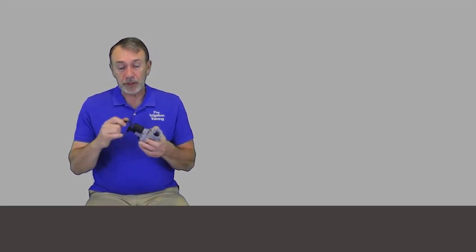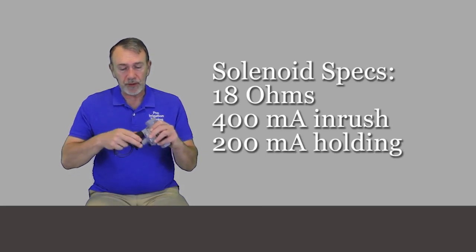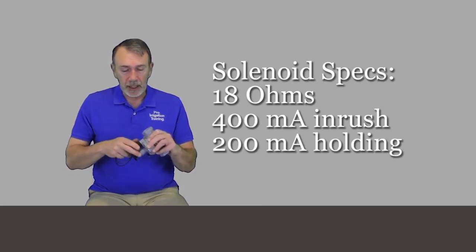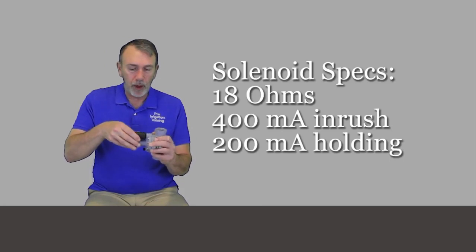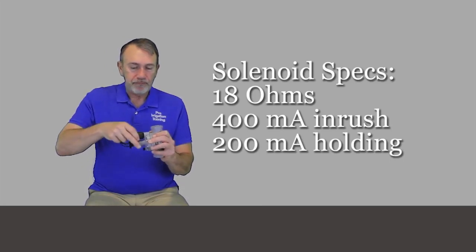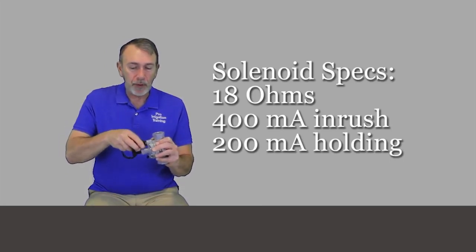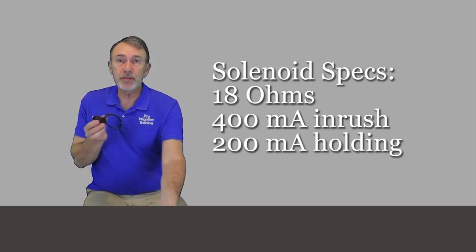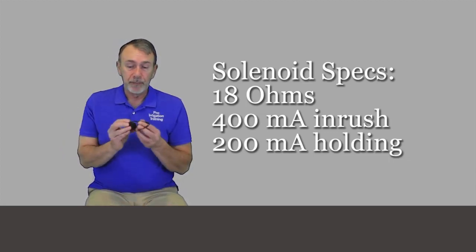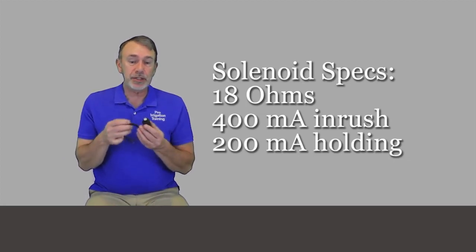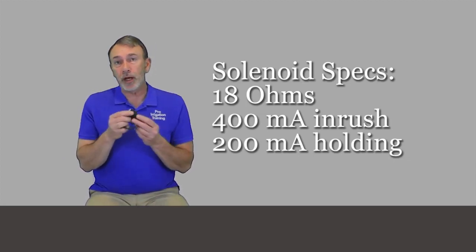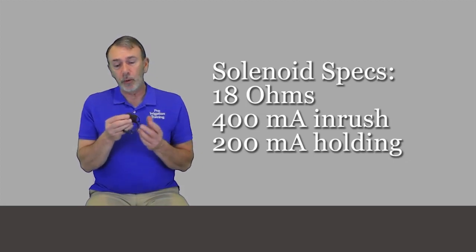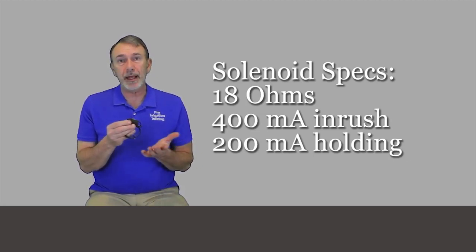Now, let's talk about the solenoid. The solenoid's interesting on this. If you're testing it with an ohm meter, you're probably going to see about 18, maybe 20 ohms for a healthy unit. For the inrush amperage to open it up is 400 milliamps, and to hold it open is 200 milliamps.